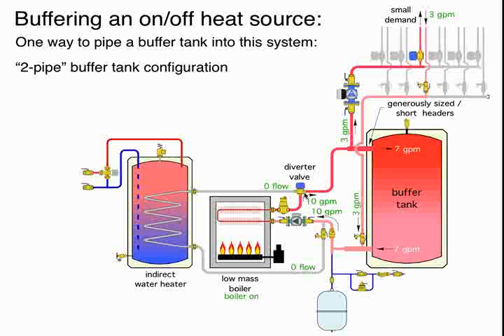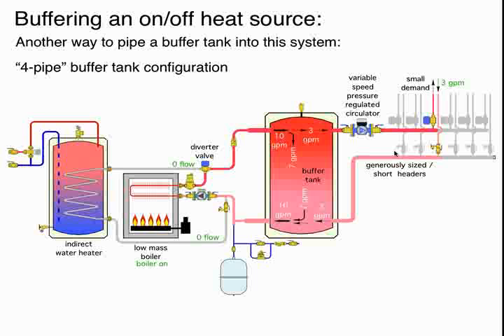Now, in this system, again, this diverter valve either allows that flow to go this way over to the space heating load or the tank, or the diverter valve allows it to go to the indirect water heater. We would probably set a system like this up for priority domestic hot water. So if we got a simultaneous call for domestic water heating and space heating, we would go to domestic water heating. But the nice thing about this system is even while the boiler is sending heat to the domestic water load, we can still extract heat. We would just reverse this arrow here. We still extract heat, send it off through our one active circuit. It would come back and right back through the tank. So even though we have priority domestic water heating, our tank can still supply energy to that heating load.